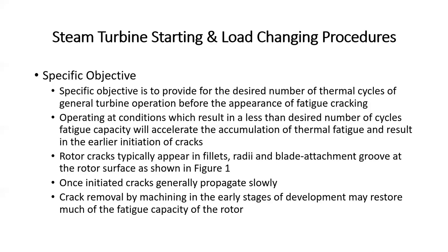In 1974, Gallatin, Tennessee had a rotor burst on cold startup. I don't know how many tons of material, but this thing came apart during operation, and parts of the rotor penetrated the inner casing. The outer casing went through the roof about 100 feet up in the air and landed a quarter mile away in the parking lot. So there's such a tremendous amount of energy here. These failures are just unacceptable. In that particular case, there was no loss of life, which was truly a miracle.